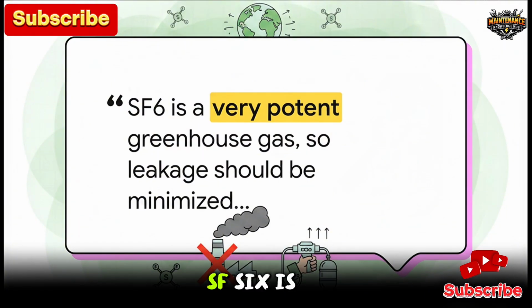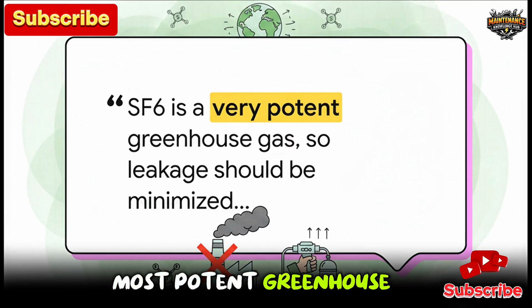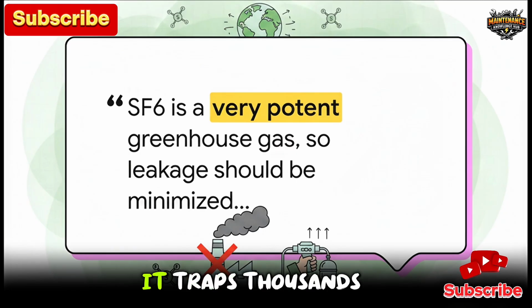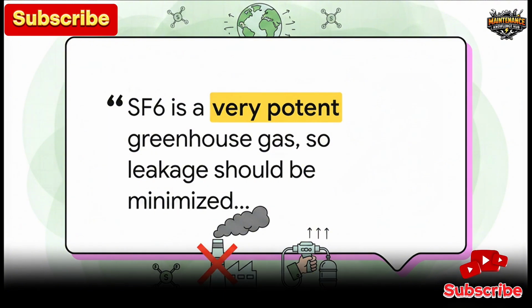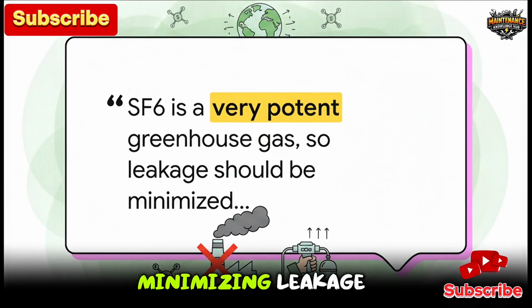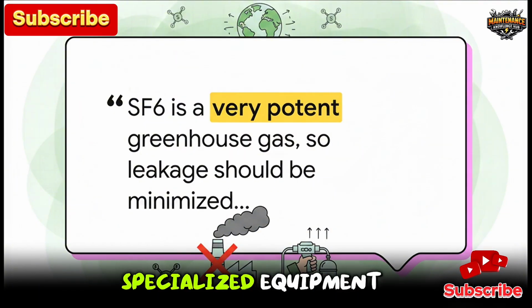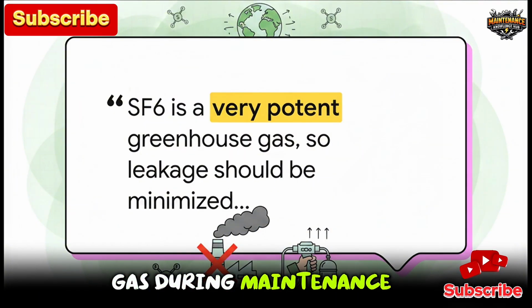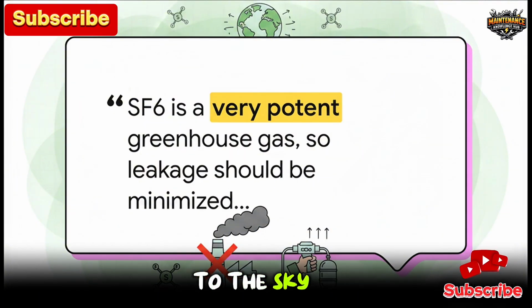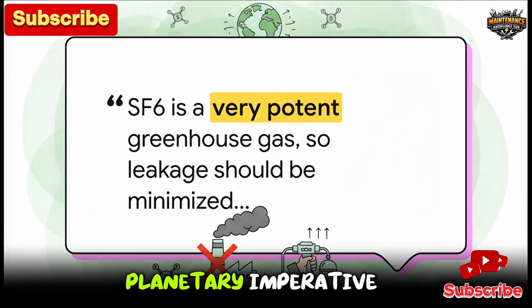But safety actually extends far beyond the technician, leading us to a major twist in this technology. SF₆ is one of the most potent greenhouse gases ever evaluated. It traps thousands of times more heat in the atmosphere than carbon dioxide over its lifespan. Yeah, thousands. So while SF₆ is a miracle safety gas for our local electrical grids, it is an extreme environmental hazard on a global scale. This means that minimizing leakage and using highly specialized equipment to recover the gas during maintenance, rather than just venting it to the sky, is literally a planetary imperative.